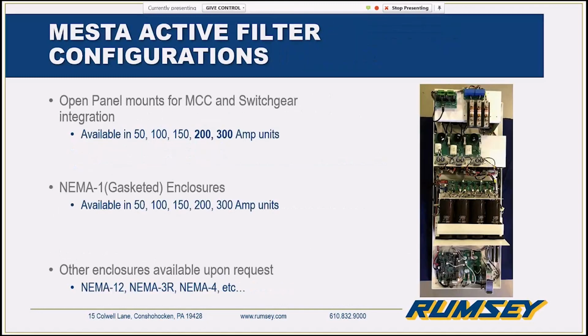And then to look at how we're configured, how do you normally get an active filter? Pretty industry standard, 50 through 300 amps. All of these are available in open panels, and that's what we provide with Rockwell putting them in their MCCs. But more frequently, we're in NEMA 1 enclosures. These then use a feeder breaker in the MCC or at the switchgear they're cabled over to. Again, 50 through 300 amps.